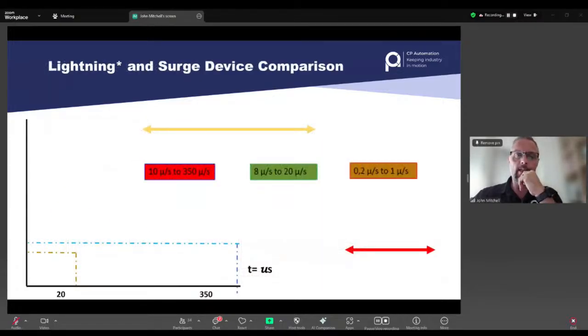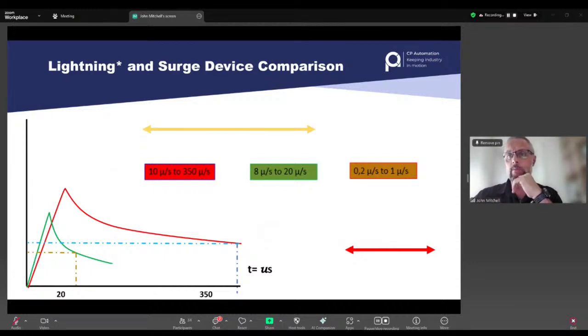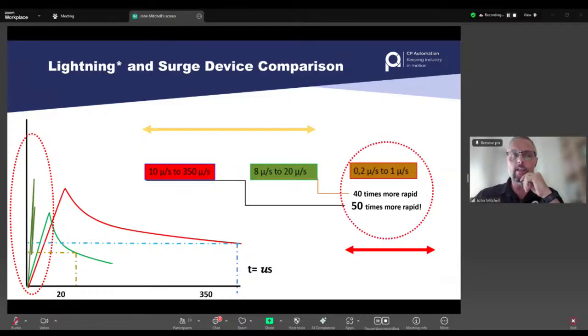So the core thing I wanted to add to Jim's presentation today is that SPDs are working in a certain area, designed around what the standards call for, because the people who wrote the standards were the people who made the product. But the reality is the transients that the sine tamer is fixing are outside that window, which is why SPDs never work for them. The sine tamer responds about 50 times faster, to something that's microseconds, sub-microseconds almost, in terms of speed, and it captures that and prevents it from becoming a high impulse issue.